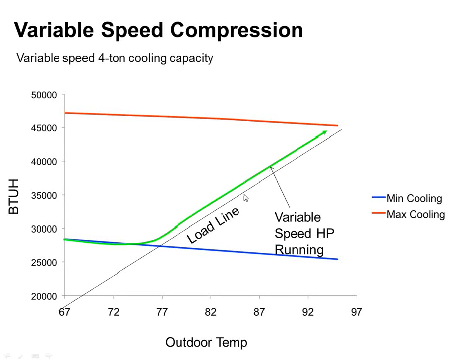So what's going to happen is, let's say it's 90 degrees outside right now. He's running over here at 40,000 BTUs. As it gets colder outside, he'll start ramping down, ramping down. He'll try to follow the load line of the house, just like we do on the heating side. He'll follow the load line until I get down to some point that I can't go any lower.